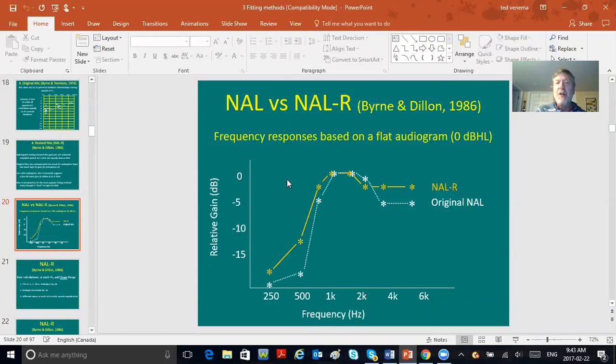Pretend someone has no hearing loss. Look at the zero. Okay? No hearing loss. Well then, how much do the low frequencies need to be reduced in order to make them sound equally loud to the higher frequencies? And NAL said, oh, you've got to reduce them by a lot. NAL-R said, yeah, they've got to be reduced, but by not quite as much. Okay, so whereas the original NAL would really back off from giving low frequency gain, NAL-R said, you're protesting too much.